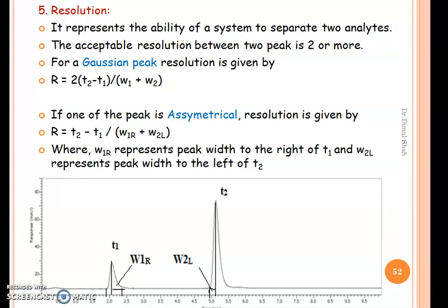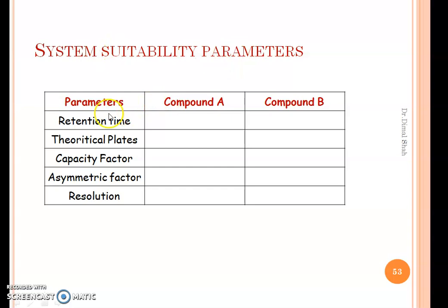System suitability parameters — retention time, theoretical plates, capacity factor, asymmetric factor, and resolution — can be reported in a table with values for compound 1 and compound 2 along with standard deviation values. Before starting routine analysis, first run a system suitability sample and check that all these parameters are within the limit, then start the quality control analysis. That is the purpose of system suitability study.